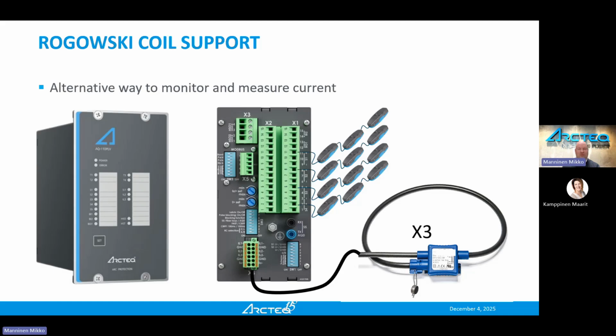So this is a well-respected way of working with these arc protection systems. No computers needed if you do standard systems. And like the current transformer versions, this one also accommodates a maximum of 12 point sensors, which are connected here in this terminal block.